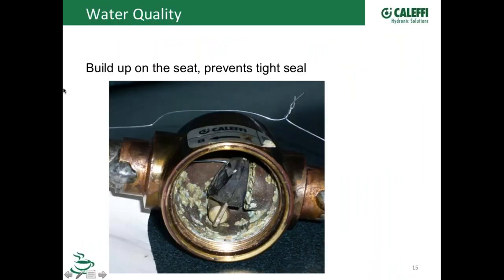Now here's a valve that was returned back to us, and they said the valve wasn't shutting off tight, we were getting leakage through it. Well, this is a case of water quality. One of my favorite topics these days when I go out on the road training is to pay attention to water quality, because you can see what's happened. There's the flapper that has to close off against what once was a nice, shiny, clean brass seat. You can see this buildup in here that's preventing that flapper from actually getting to the brass seat, and the valve's leaking through. Maybe that was an open system that had a lot of fresh oxygenated water with a lot of minerals constantly being added to the system, but that's not a valve defect. Obviously, you can see the little return tag on it here. That's a condition that was caused by the application.